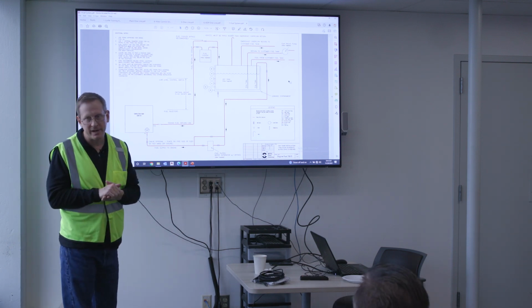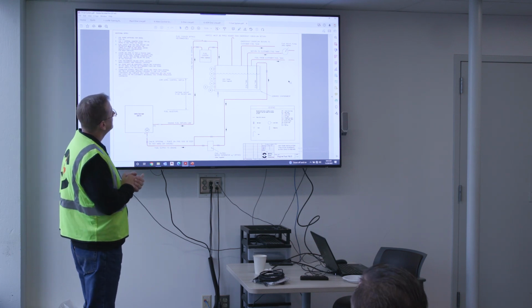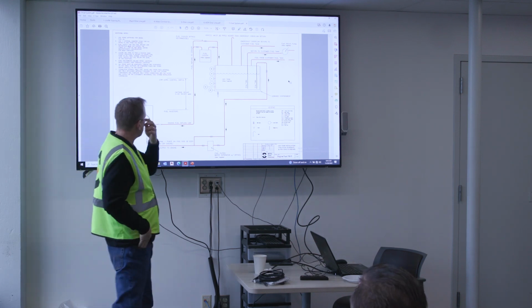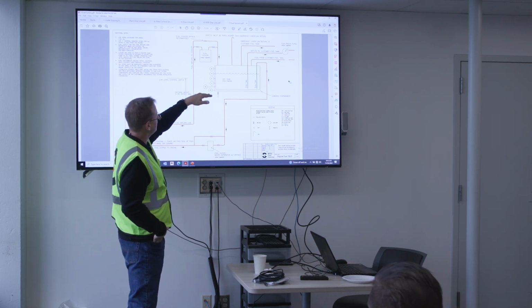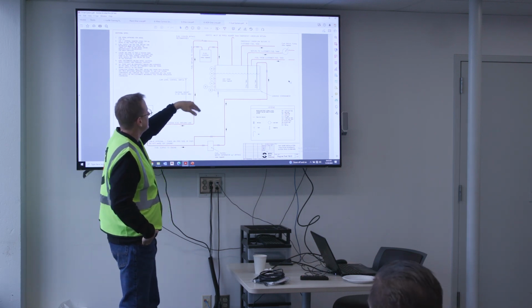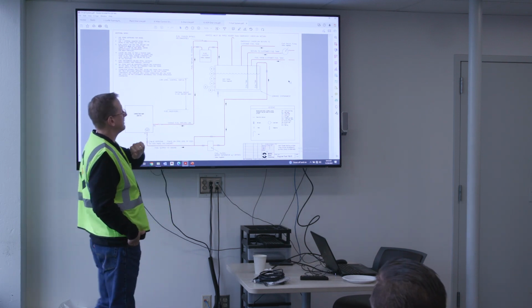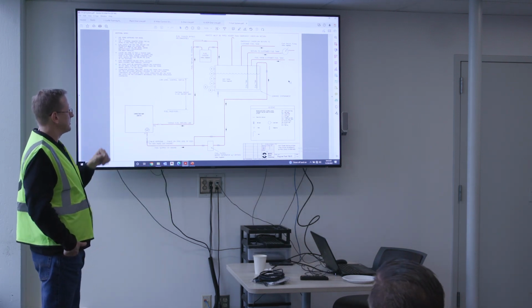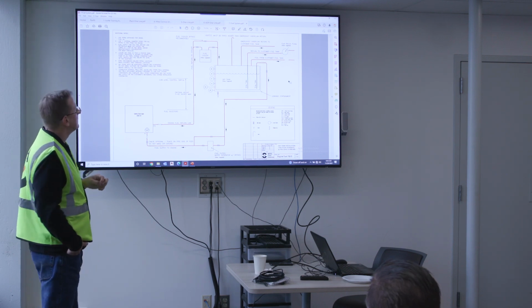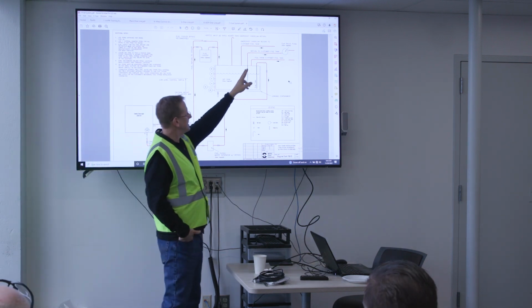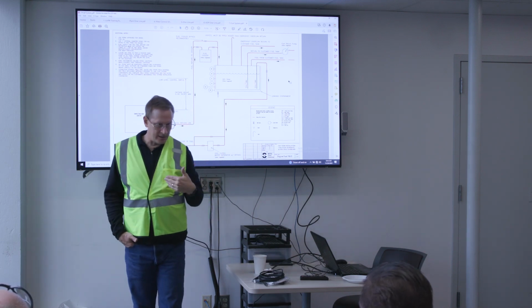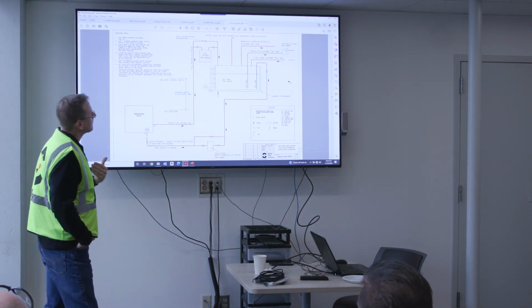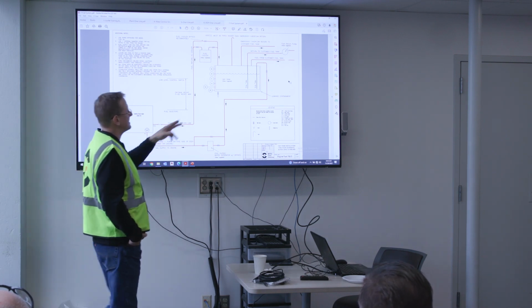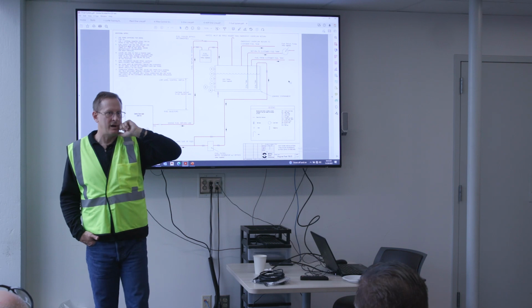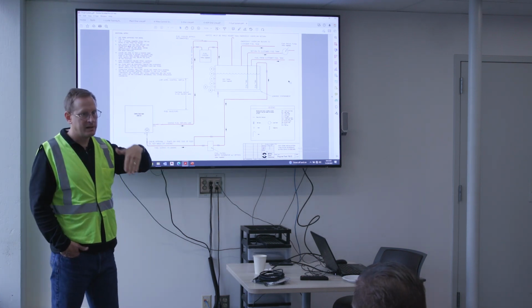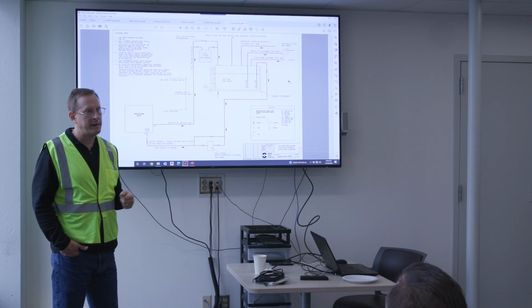It's one of our action items held over from last week. So again, low level alarms we get from the tank, high level alarms we get from the tank. Critical high will start a return pump, and we'll start returning fuel from the day tank back into the main tank. We have 2 sets of valves that will open to receive fuel from your bulk tank, and we also have 2 sets of valves for emergency stop, for emergency shut off. Again, if we get that high level indication, we're going to tell those valves to close and start pumping fuel back out into your main tank.